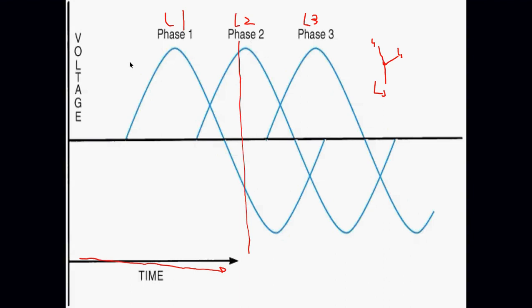So if I have a single-phase motor with a capacitor driving a compressor, my amperage under full load, just tossing a number out there, let's say it's running at 14 amps. If I take that 5-ton compressor and replace it with a 3-phase 5-ton compressor, I could effectively cut my amperage in half.